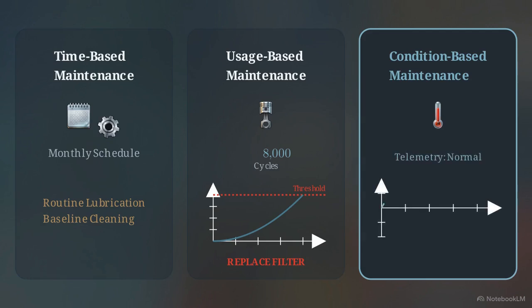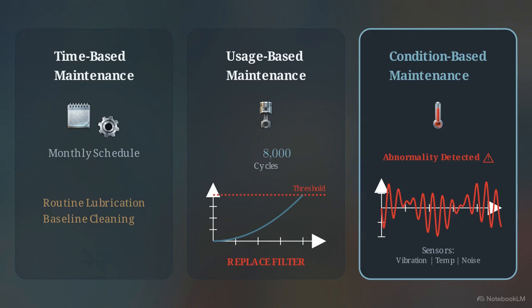The third framework is condition-based maintenance. This relies on real-time telemetry. Sensors monitor vibration, temperature, and acoustic noise, triggering a maintenance event only when physical abnormalities are detected.